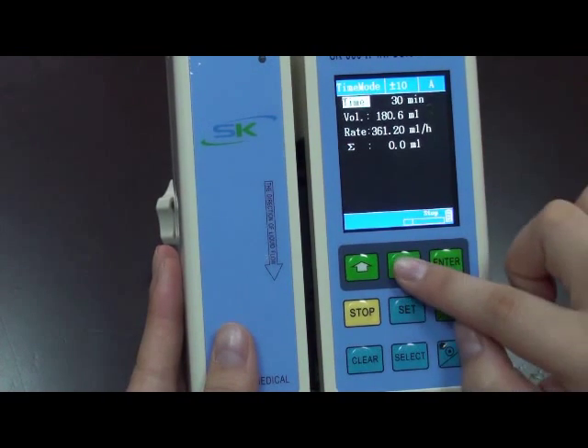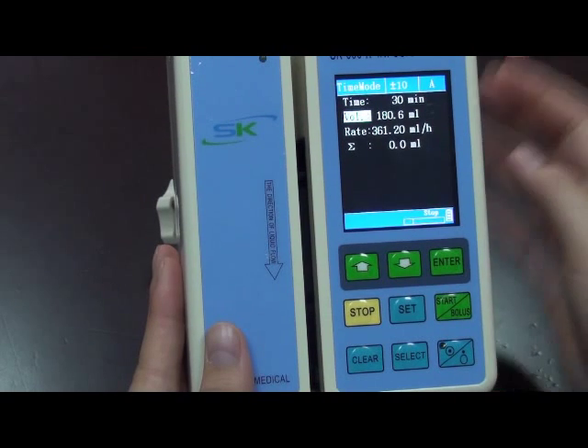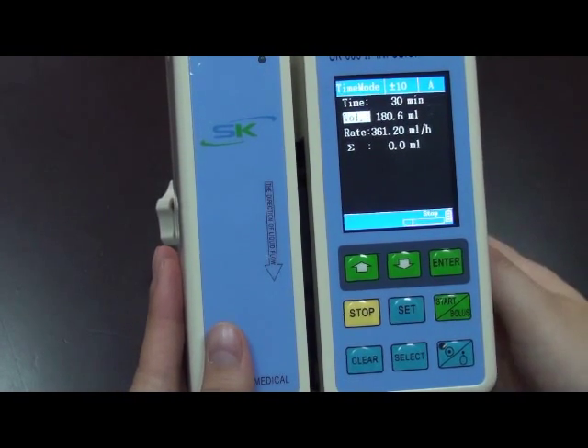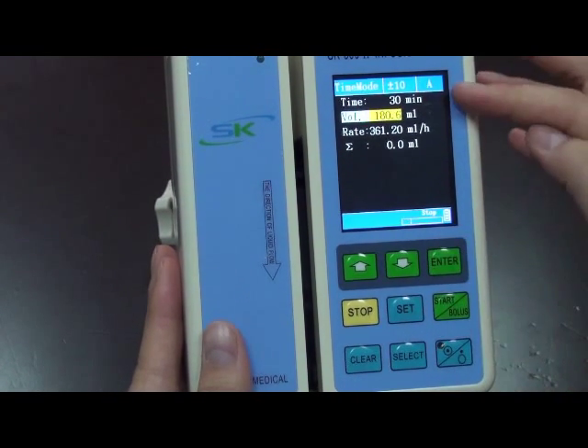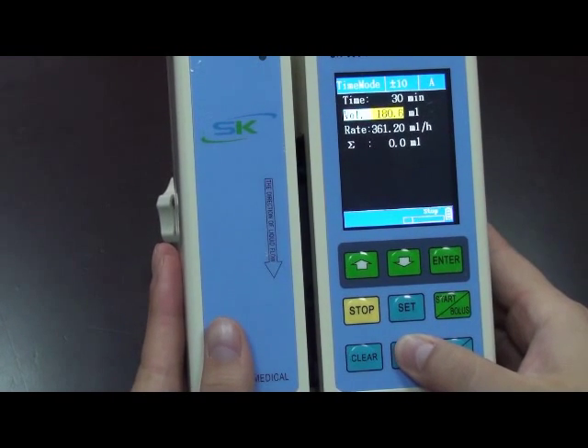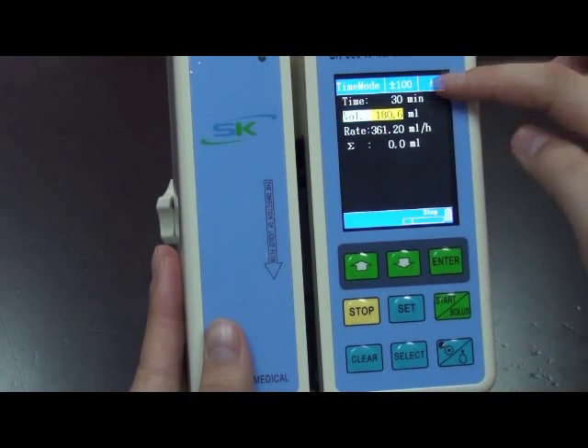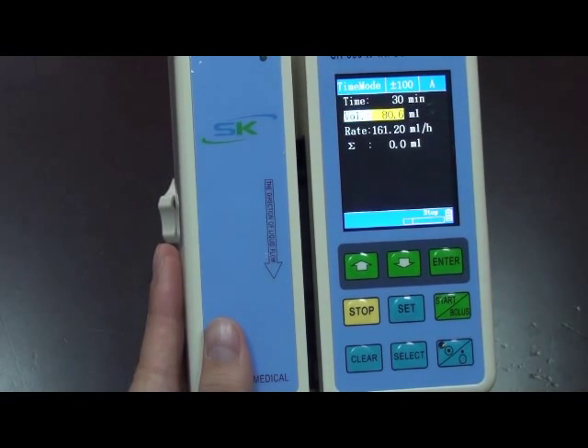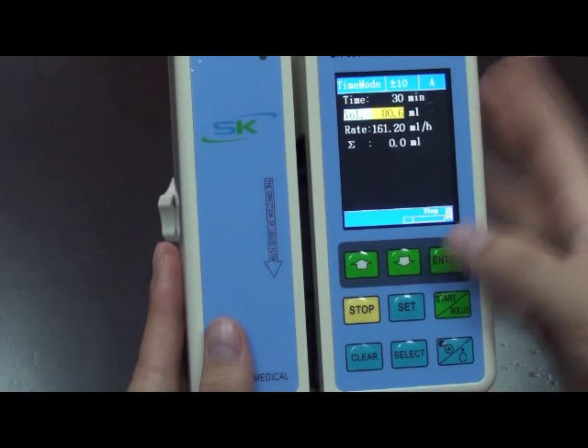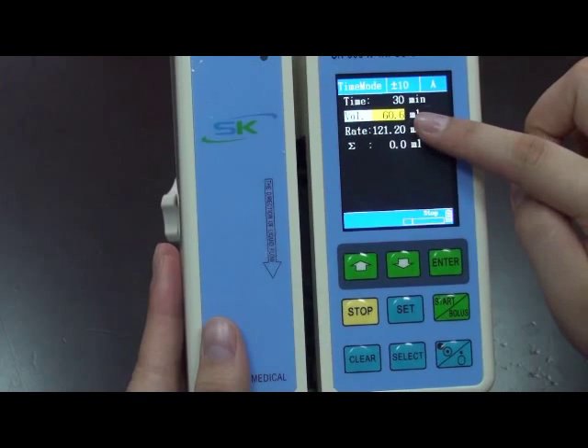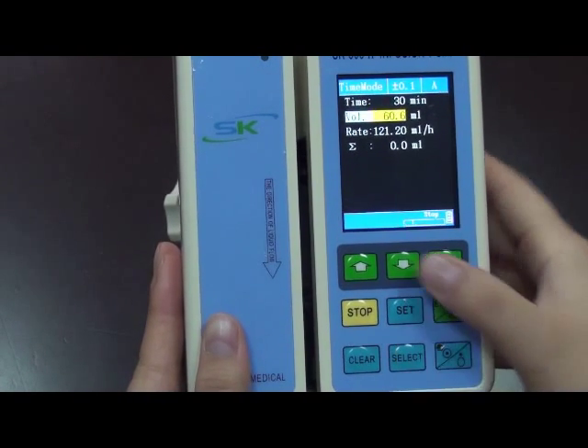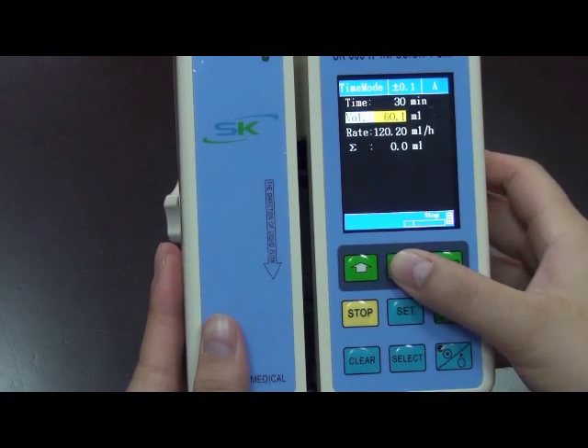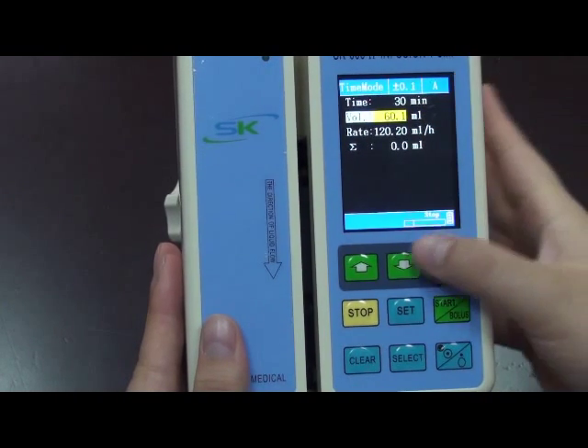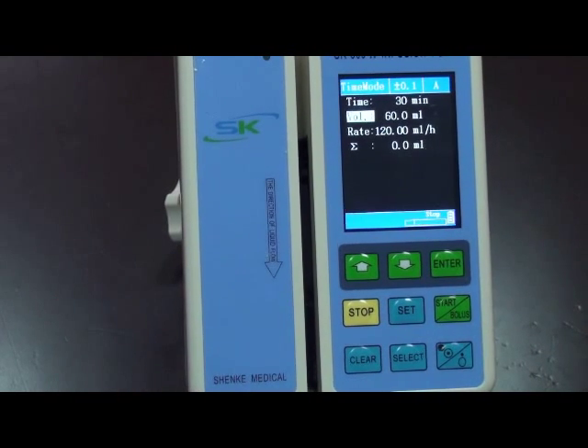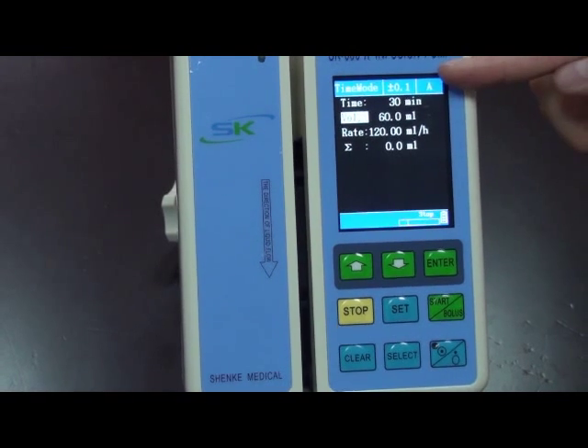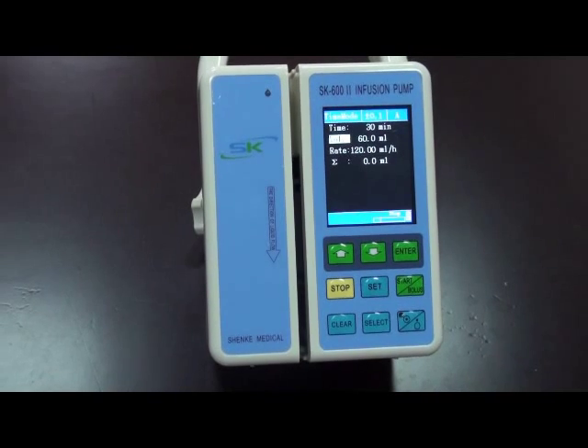Press Enter key again. Now press down key to choose volume. She wants the volume to be 60 ml. Now it's 180.6. So she presses Enter key to choose this parameter first. Then press Select key to choose 100. Press down key once. The value will reduce by 100. And then choose 10. Press down twice. See, it reduced 20. Also, you can observe the rate is changing while I change these 2 values. After we set the time and the volume, the rate can be calculated automatically. This is time mode.